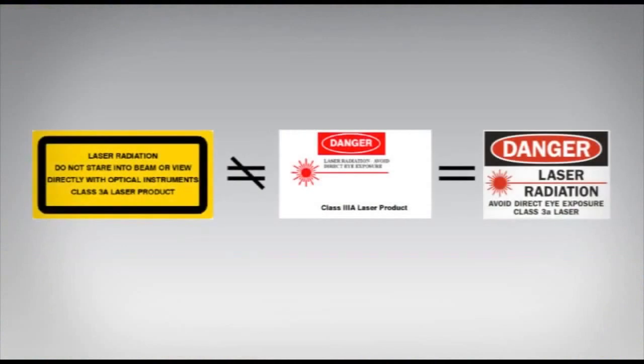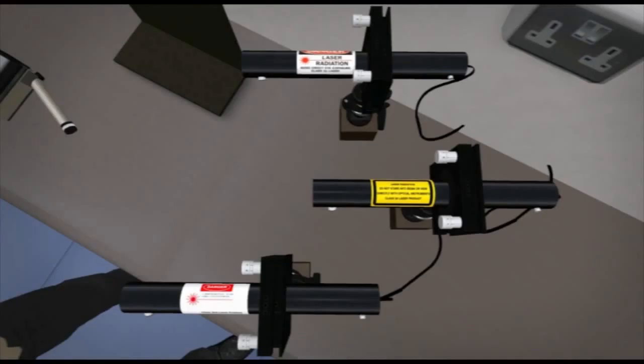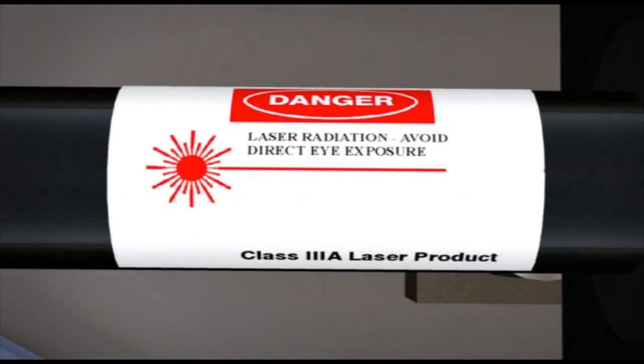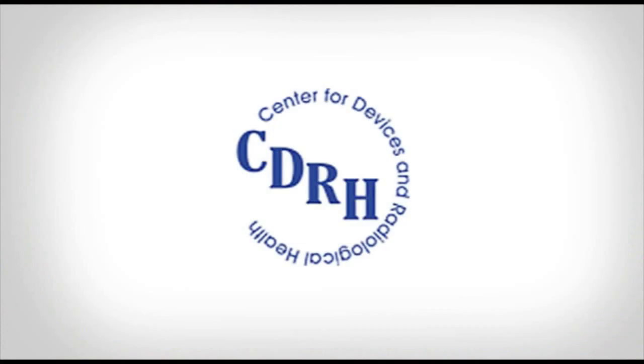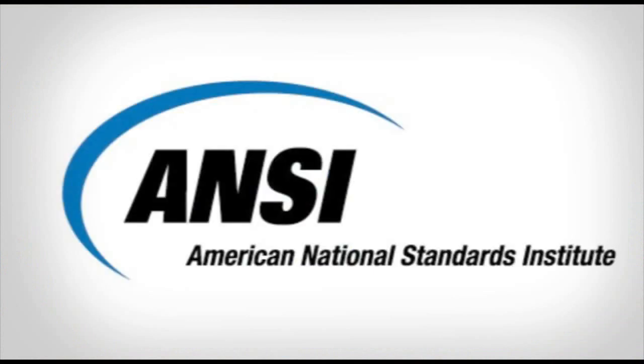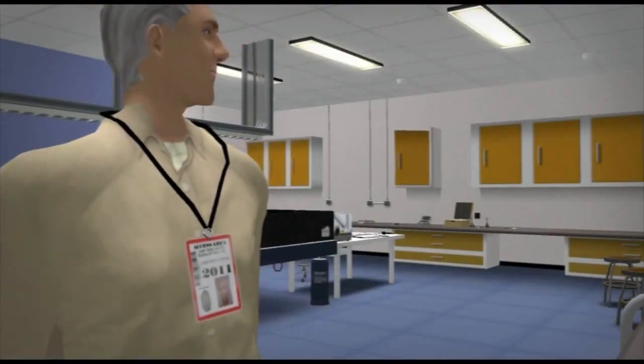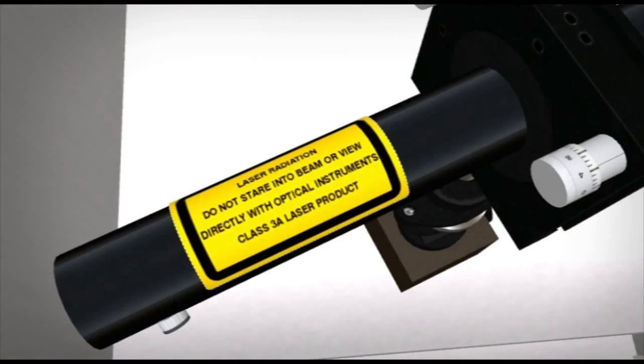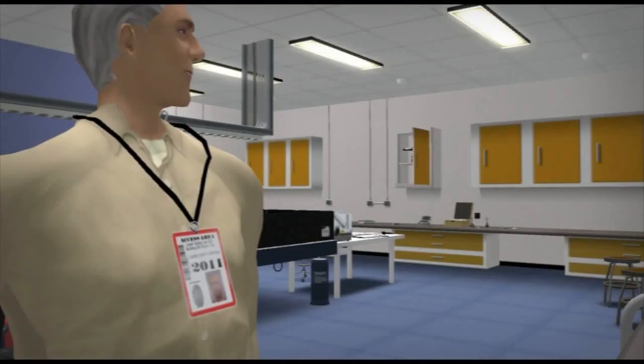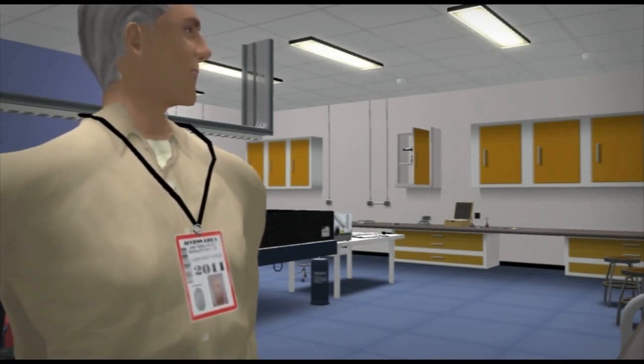It is important to understand the differences between upper and lowercase characters and Roman numerals that are used to identify the different types of lasers. These can signify that a laser is labeled according to a different classification system, such as the CDRH or ANSI system used in the United States. Be aware that old lasers may use legacy labeling systems, which do not map easily onto current classification. Speak to your laser safety officer to ensure users are familiar with what different labels mean and how lasers can be disposed of safely.